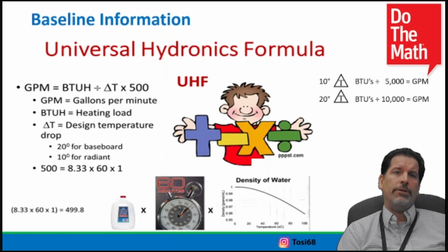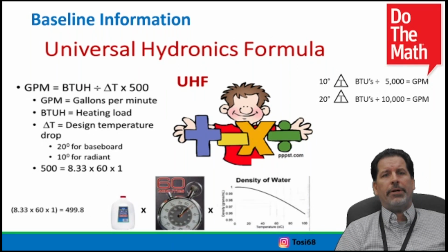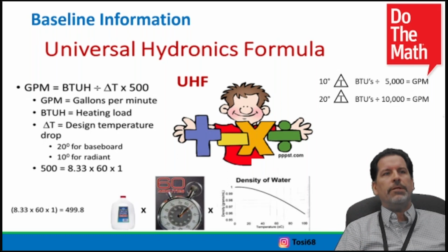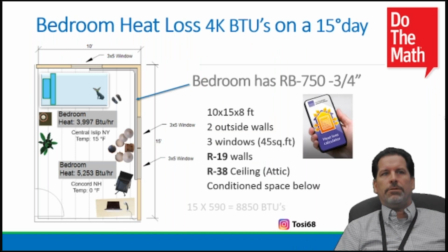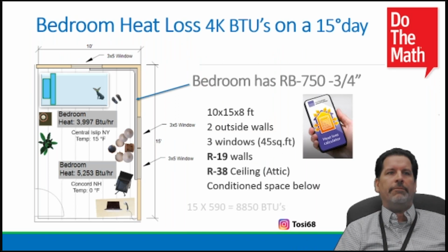We then can go back to our circulators, and we can even make a better selection and make sure we are delivering to achieve somewhat of that delta T that we're shooting for. Not always easy. We get close, but for the most part, this is where it all starts. Universal hydronics formula. Now, I did a heat loss, as we do. We have programs. If you've never done a heat loss, and you do your first one, I would say do your own home, become a mad scientist in your own home, figure out what your rooms require, what the total house requires, then go back to the boiler and go, wow, what a difference. Trust the numbers.